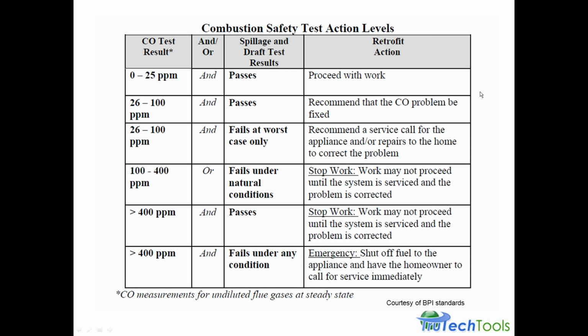This isn't a full course in spillage and draft testing, but I did want to give you an idea of how the CO test results play into a combination of spillage and draft, because we did talk about CO production and also ventilation and draft, talking about the required amount of air, in addition to causing CO to be produced due to insufficient combustion air or dilution air. It can also affect the way the draft system or the vent system operates. So here's where these two factors come together: both insufficient amounts of air causing CO, as well as impacting CO getting out through the vent system.